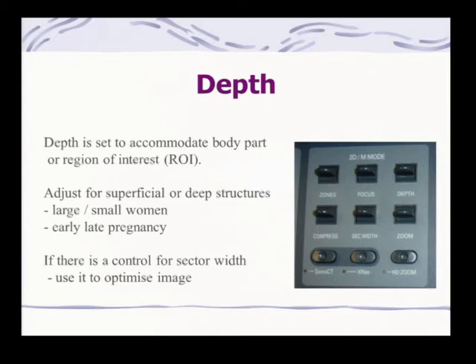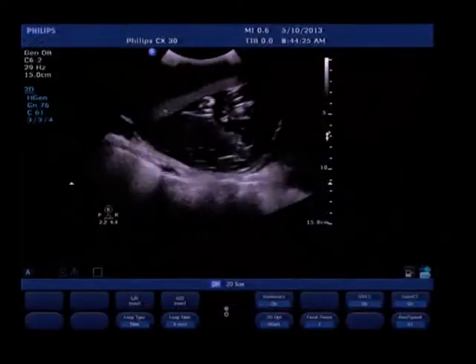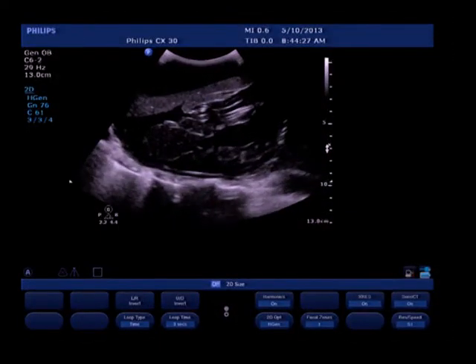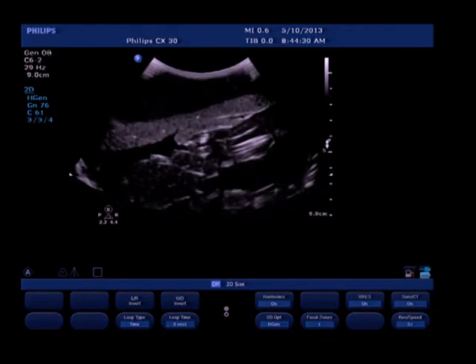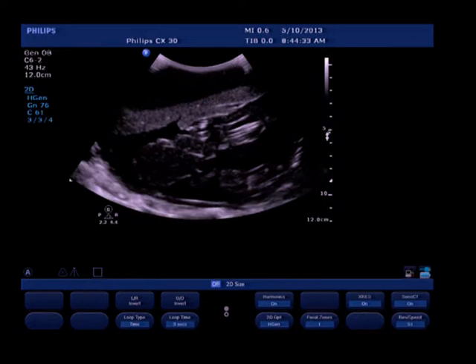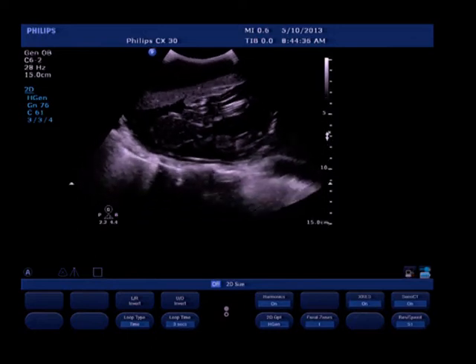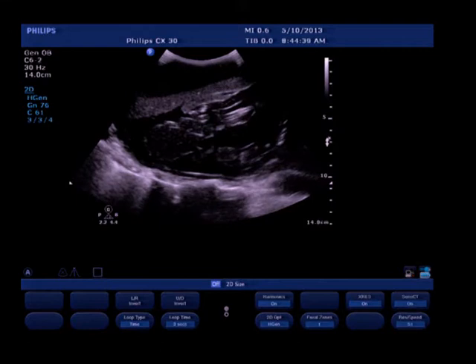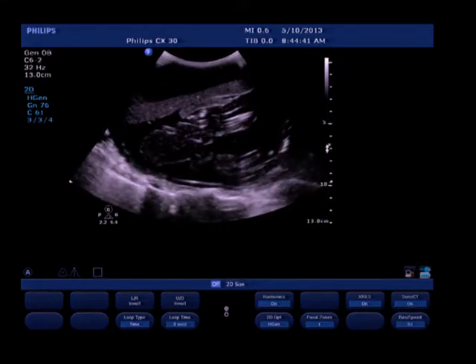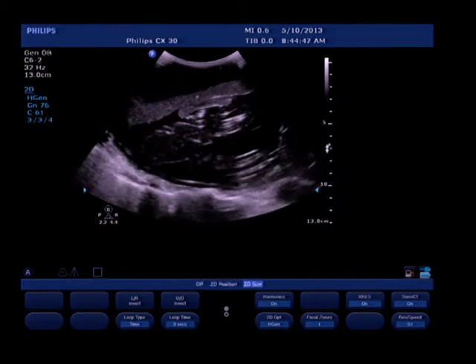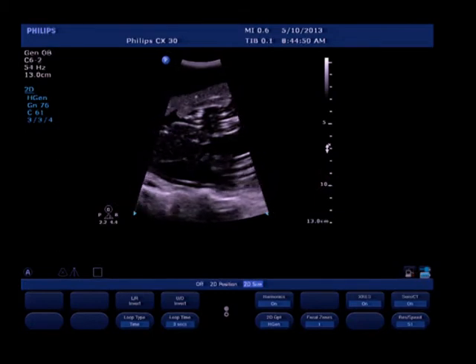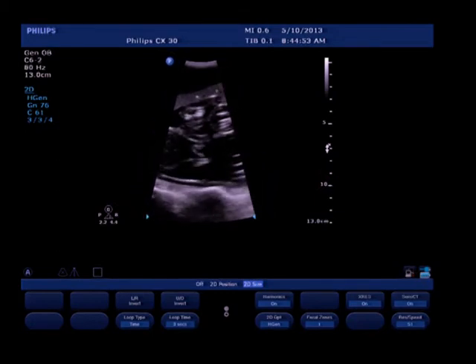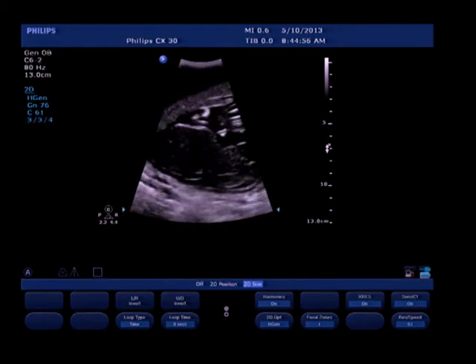And if there's a control for sector width, we should be using that as well. Now I'm just going to flick across, Tracy, to show, so you can show them the depth and the sector width. So watch what happens when she adjusts that. You can see we're coming up to the near field. And if you look at this control just at the side, what we call the focus, there's a little arrow at the side there. That's the focus. And do you have sector width on that, Tracy? And sometimes if you're looking at a very early gestational sac, it's worthwhile bringing your sector angle straight in and also adjusting your depth.